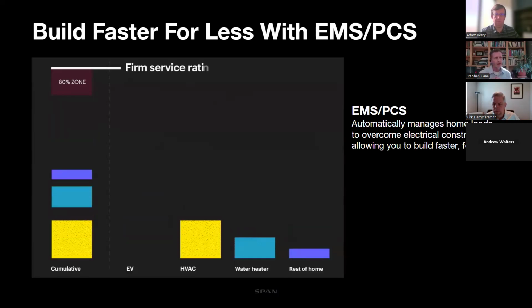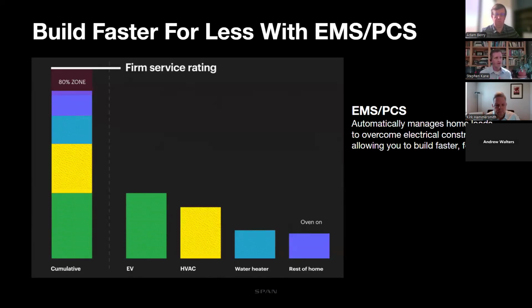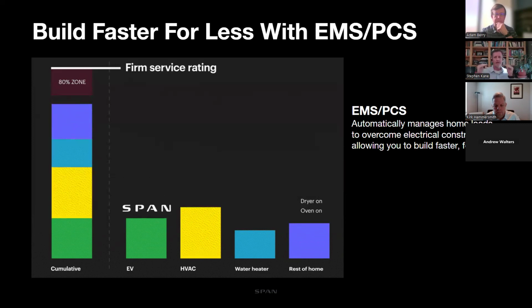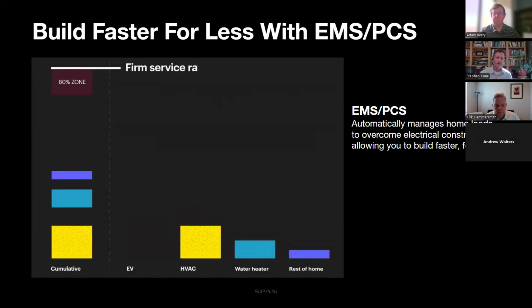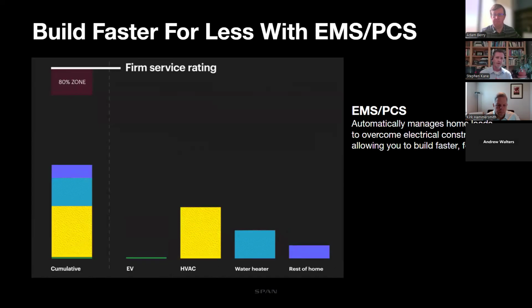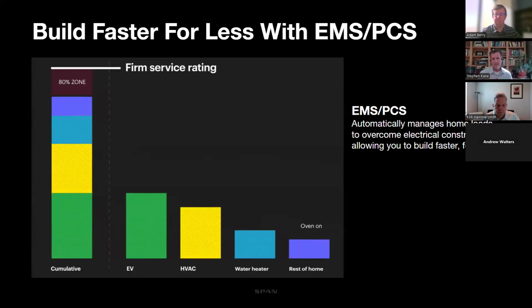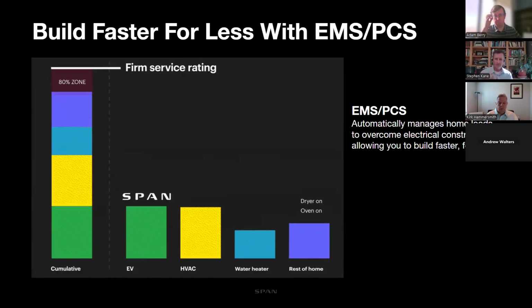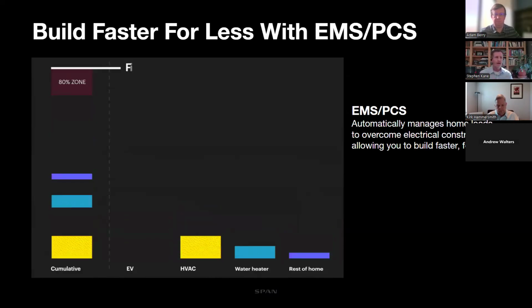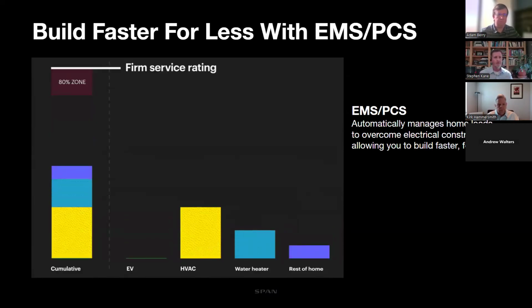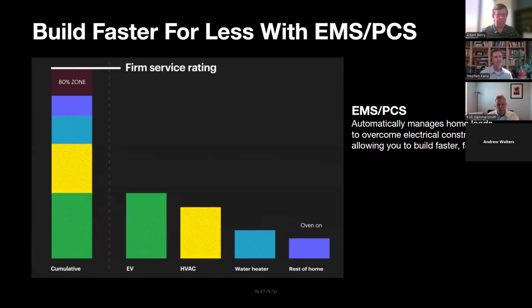And so framing it in that way, you can kind of see that we have this concept of a firm service rating as we start adding more load: turning on the EV when you come home from work, kicking on the oven to get dinner going. You start to reach that 80% threshold, so 160 amps on a 200 amp service. And ultimately, something needs to reduce its consumption so that we don't trip the main breaker. In this case, the EMS can either completely turn off a load by opening a relay, or it could dynamically curtail it by communicating with an API. And ultimately, we keep the load on the service within bounds.